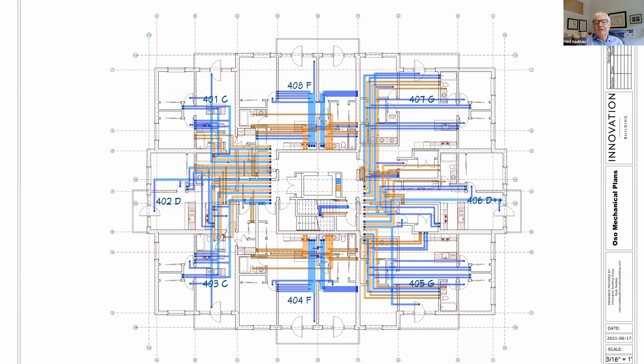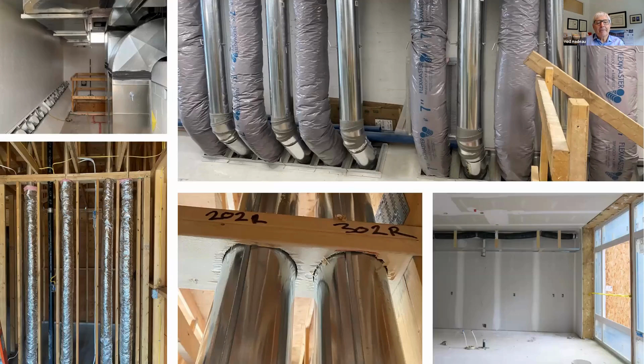This is a full-scale plan of the HVAC ducts in the rooftop mechanical room and attic space. They all fit in the walls and drop straight into the units. We overlay this on the structural plans and design out all the conflicts, then add the plumbing stacks, sprinklers, and water mains, so every trade gets their space with no conflicts. Here's the mechanical room ready to hook up the individual ducts from each unit to the central distribution, with duct runs with a balancing damper that are accessible in the mechanical room.